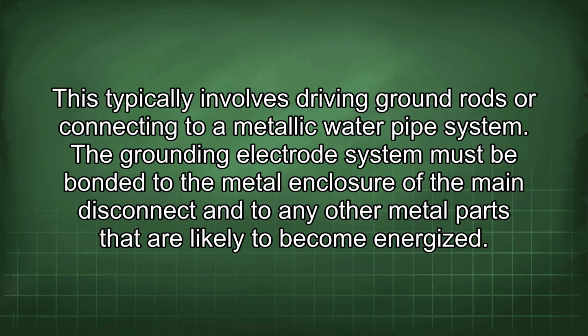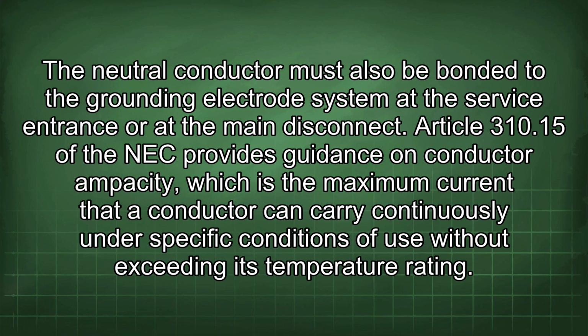The grounding electrode system must be bonded to the metal enclosure of the main disconnect and to any other metal parts that are likely to become energized. The neutral conductor must also be bonded to the grounding electrode system at the service entrance or at the main disconnect. Article 310.15 of the NEC provides guidance on conductor ampacity, which is the maximum current that a conductor can carry continuously under specific conditions of use without exceeding its temperature rating.